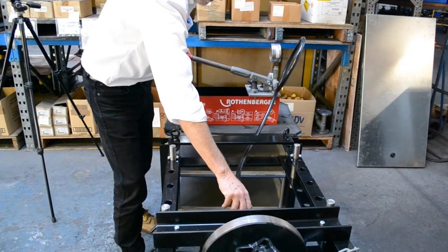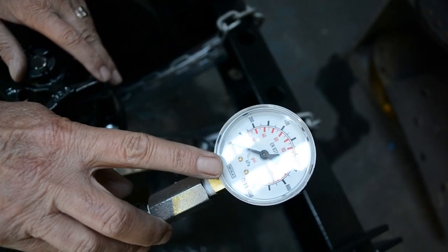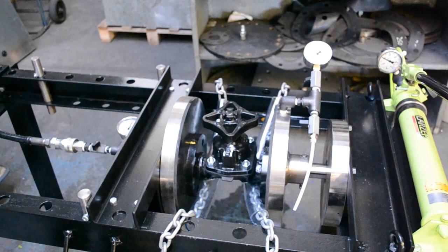Operate the inlet pump until the gauge reaches 1.1 times line pressure and close the inlet valve. If pressure remains at zero, the valve has passed the seat test.